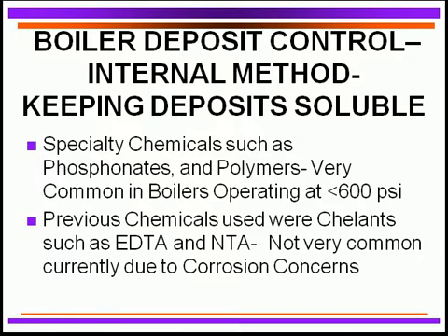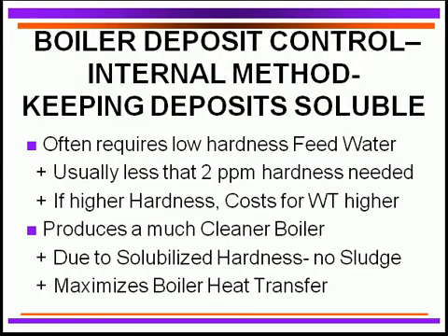Another technique used in past years, though less common now, is the use of chelants known as EDTA (ethylenediaminetetraacetic acid) and NTA (nitrilotriacetic acid). These have been common chelants historically, but are much less used today due to corrosion problems associated with overfeeding EDTA and difficulty of control. They are sometimes still added in conjunction with polymers.